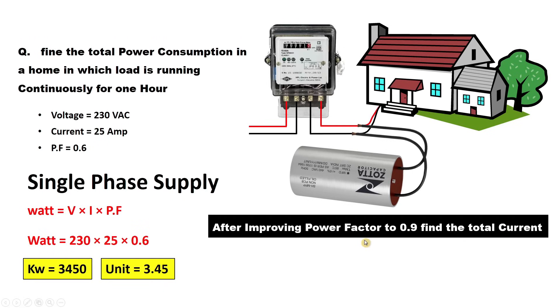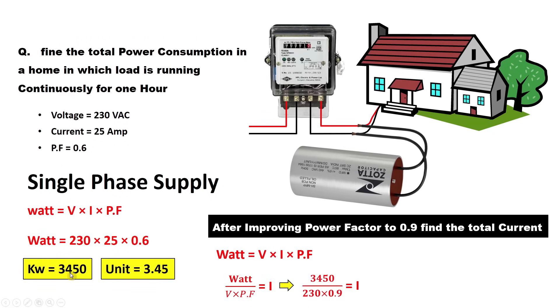After improving the power factor by connecting the capacitor, there are changes in current. Using the same formula to find current — with power as 3450 watts, voltage as 230 volts, and the improved power factor of 0.9 — the current comes out to 16.66 amperes. Previously the current was 25 amperes, but after connecting the capacitor, it is reduced to 16.66 amperes.